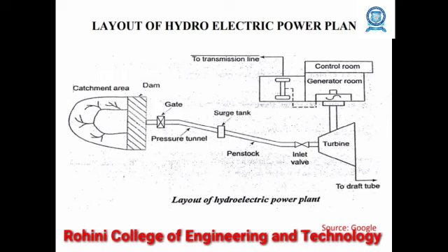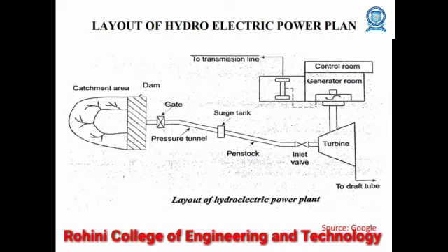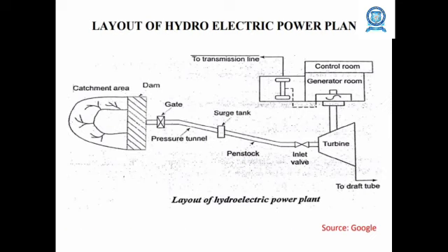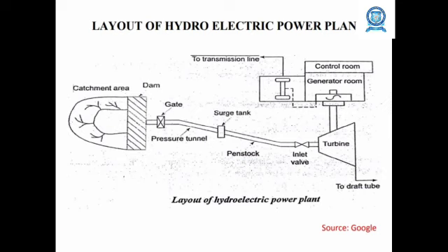Water from the reservoir is delivered to the turbines through the intake, that is, the dam gates and penstock. A filtering system at the intake further cleans the water to ensure that it is relatively free of suspended solids which could damage the turbine blades. The hydraulic system, the governor, the brakes, the gate controls and so on work together to open and close the aperture that allows water to flow downstream from the reservoir.